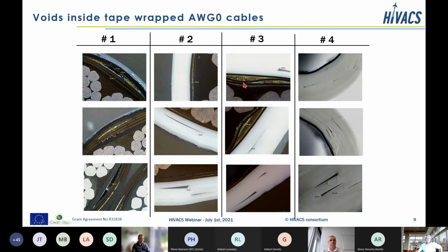insulation. In addition to the voids in the polyimide insulation, we also have voids in the PTFE insulation at the overlap of the different tapes. And here for the thick cable with 2.7 millimeter insulation thickness, we have a lot of overlaps and hence a lot of voids inside the insulation.